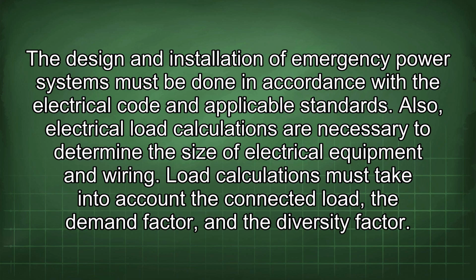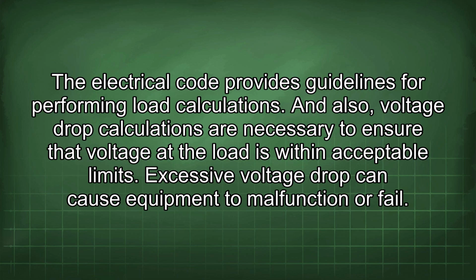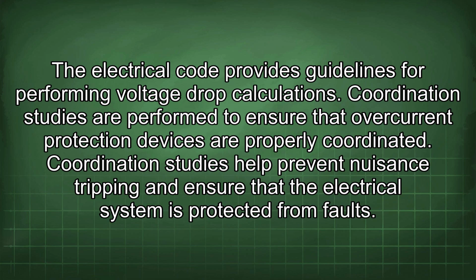Also, electrical load calculations are necessary to determine the size of electrical equipment and wiring. Load calculations must take into account the connected load, the demand factor, and the diversity factor. The electrical code provides guidelines for performing load calculations. And also, voltage drop calculations are necessary to ensure that voltage at the load is within acceptable limits. Excessive voltage drop can cause equipment to malfunction or fail. The electrical code provides guidelines for performing voltage drop calculations.